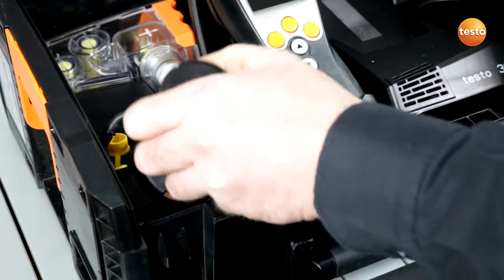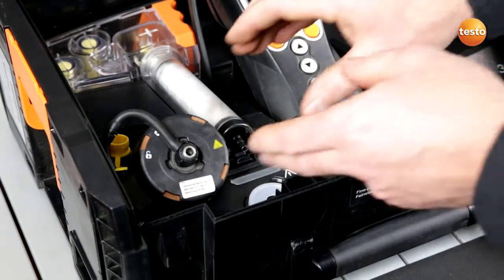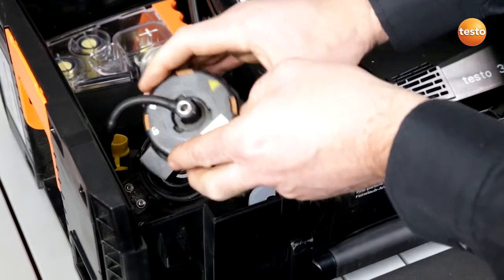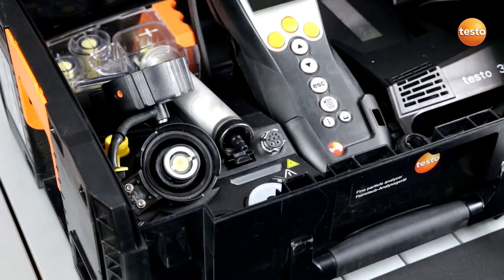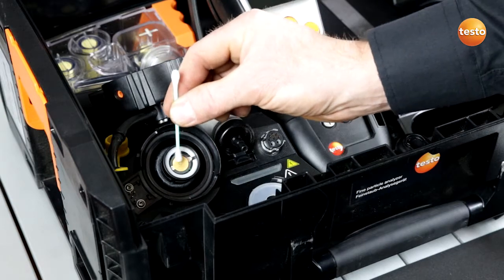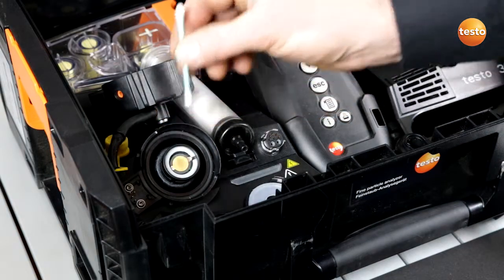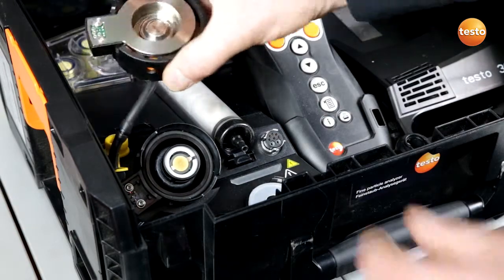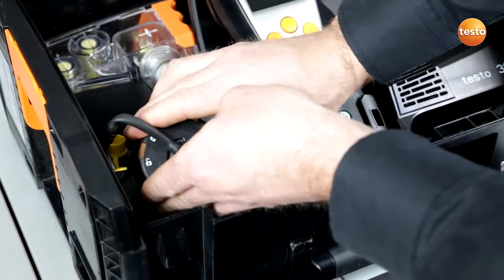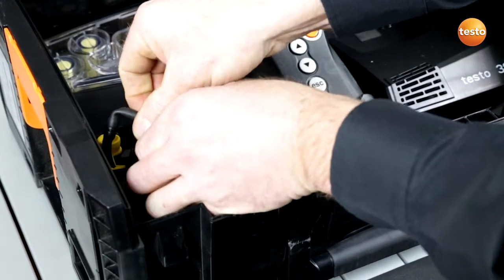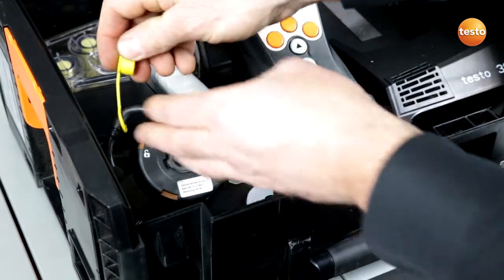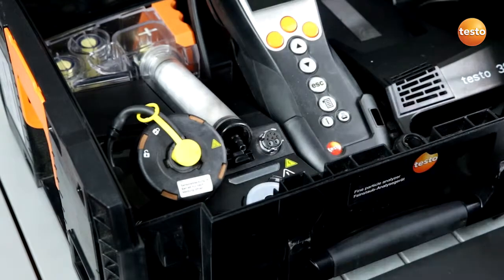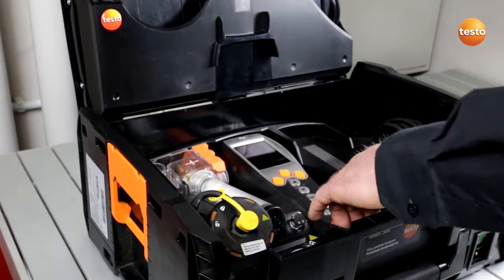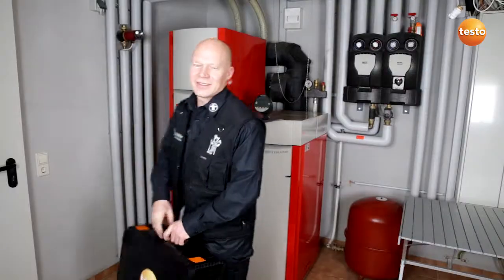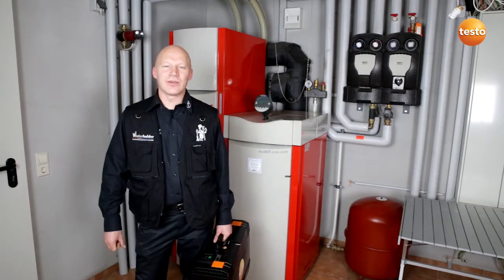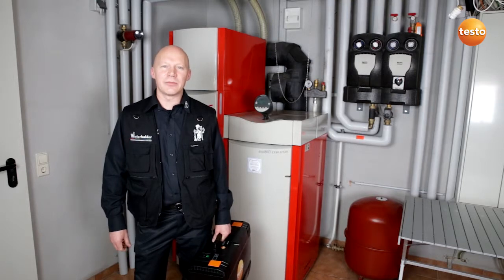To do this, I remove the preheating section, open the sensor cover, take a Q-tip and try to clean it with a light pressure. After successful cleaning, I close the sensor module cover, replace it, and turn it clockwise. Seal it with a protective cap, and the cleaning procedure is finished. The fine particle measurement with the Testo 380 is successfully finished. As you can see yourself, the limit values prescribed by law have been adhered to.